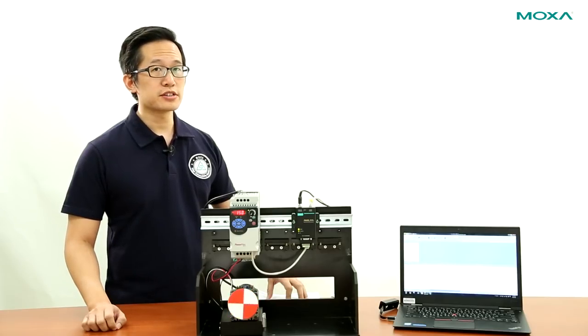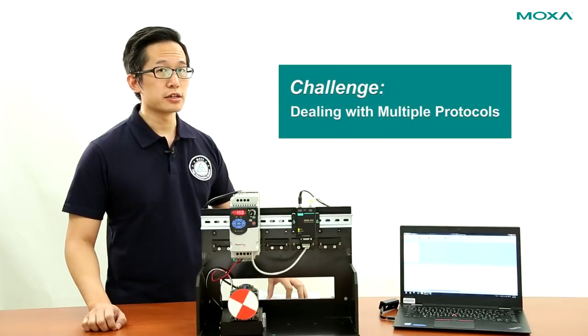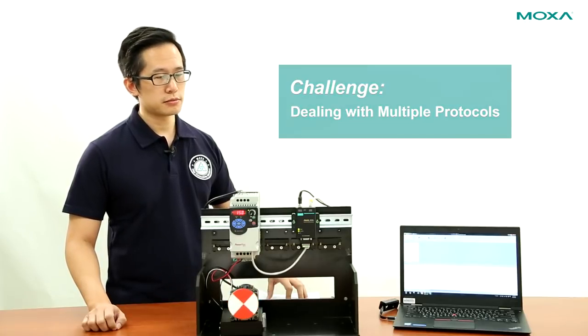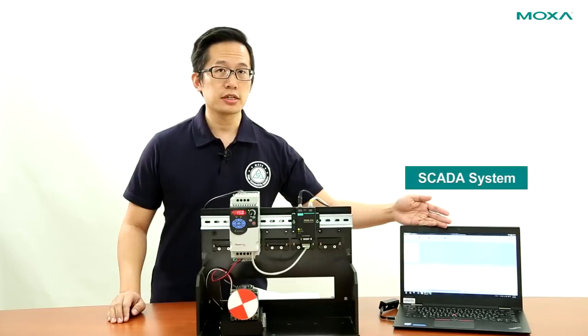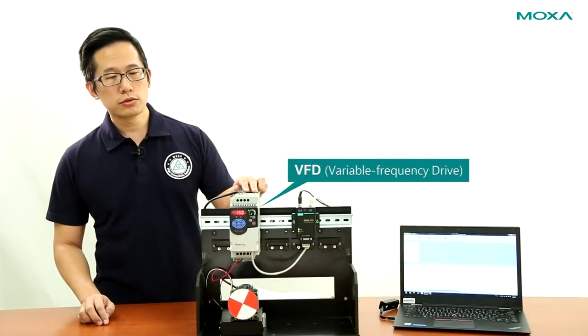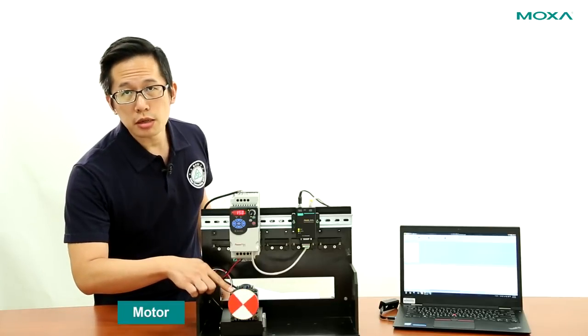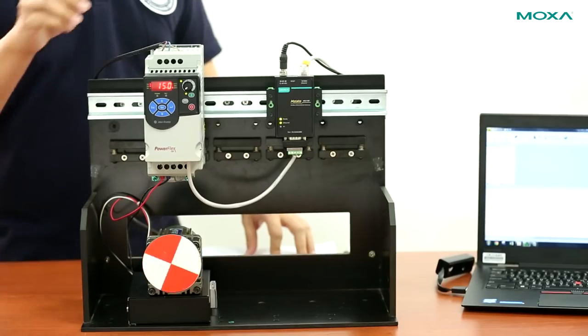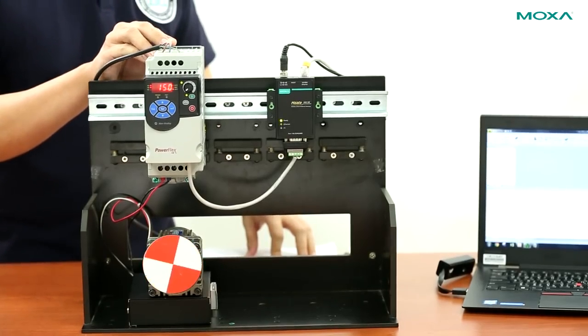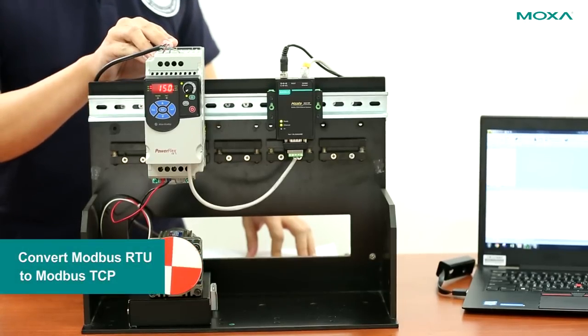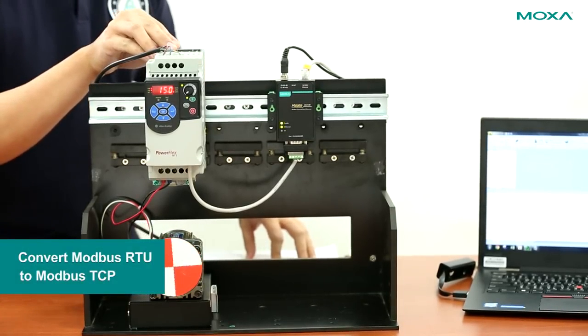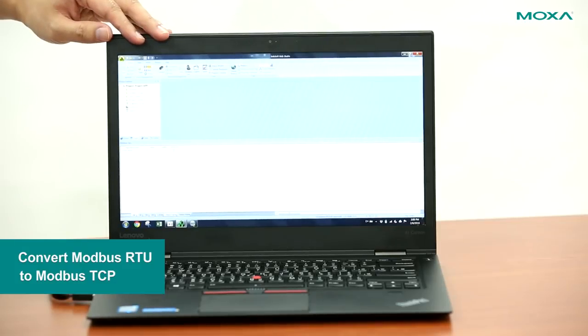Integrating legacy devices into your control network can be a challenge due to the protocols involved. Here, we have a PC running the SCADA system, and we have a VFD, which is powering a motor down here. In order to connect this VFD to the control network, we have to convert Modbus RTU protocol, which the VFD uses, to Modbus TCP protocol, which the SCADA system uses.